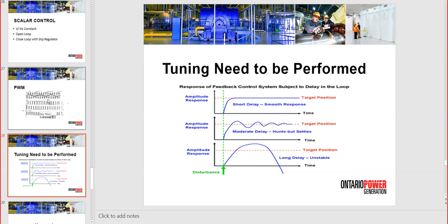So that will be always there. Another characteristic of the vector is tuning. So most of the time, because it's a closed loop control, you need to do tuning, which means you need to match the regulators of the speed or torque with the process. If it's a proportional integral, the proportional will be correlated with the torque of the shaft, and the integral with the inertia of the load of the shaft. That's why you put a gearbox. The higher the ratio, the less the motor will feel the inertia change.